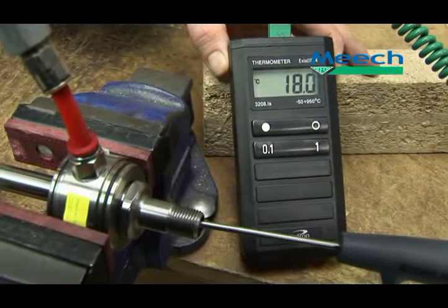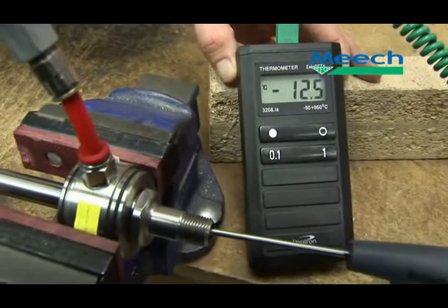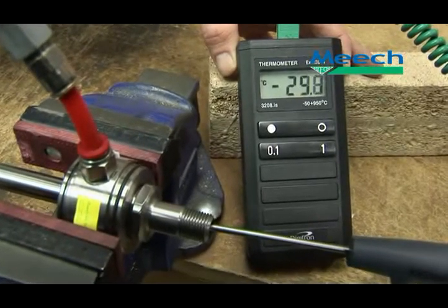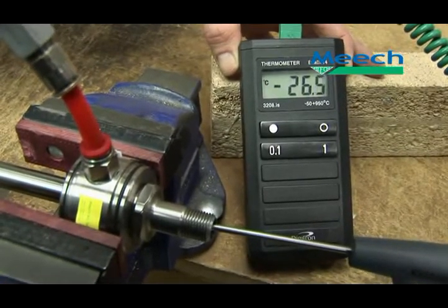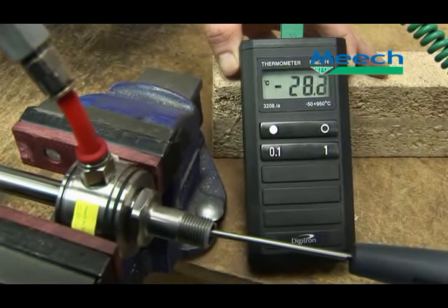Vortex tubes are extremely effective at cooling compressed air. The following film shows a compressed air supply connected to a Vortex tube. As the reading on the temperature probe shows, the temperature immediately drops when the air is turned on. It then only takes a matter of seconds to fall below minus 10 degrees C. It then continues to drop to the minimal level achievable with the chosen generator fitted. The control valve can be used to set the desired airflow and temperature.